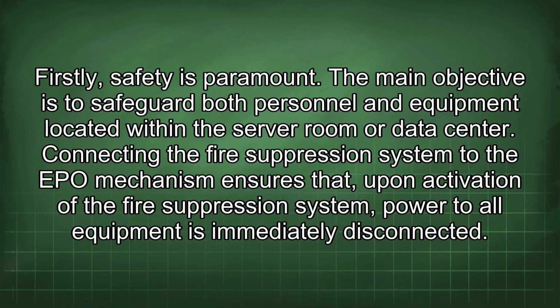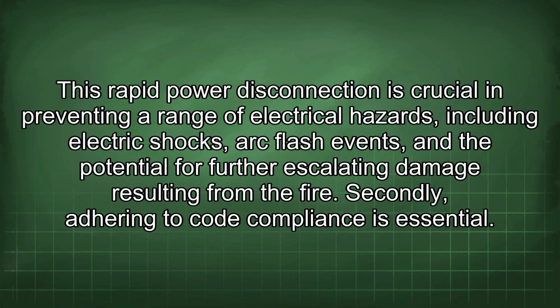Firstly, safety is paramount. The main objective is to safeguard both personnel and equipment located within the server room or data center. Connecting the fire suppression system to the EPO mechanism ensures that, upon activation of the fire suppression system, power to all equipment is immediately disconnected. This rapid power disconnection is crucial in preventing a range of electrical hazards, including electric shocks, arc flash events, and the potential for further escalating damage resulting from the fire.